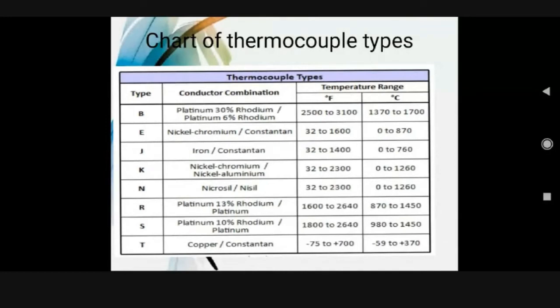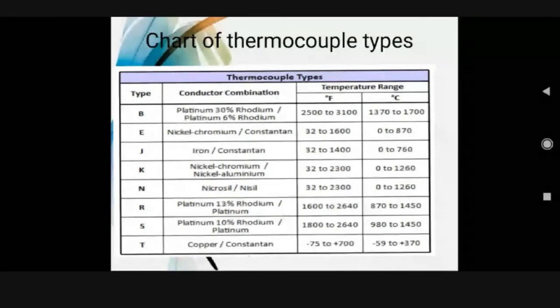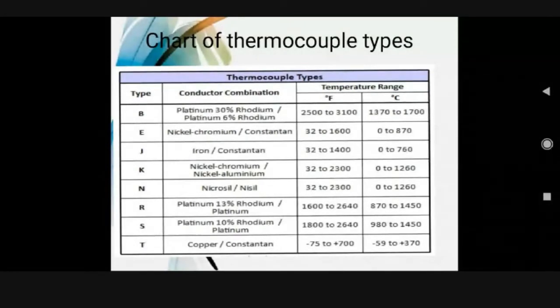Type R, platinum 13% rhodium and platinum, 1600 to 2640 Fahrenheit and 870 to 1450 degrees Celsius. Type S, platinum 10% rhodium platinum, 1800 to 2640 Fahrenheit and 980 to 1450 degrees Celsius. Type T, copper constantan, minus 75 to 700 Fahrenheit, minus 59 to 370 degrees Celsius.